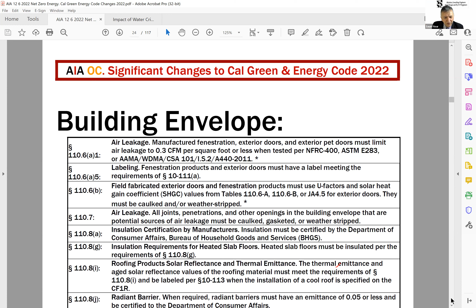There was one item I'm going to beg all of you about: slab edge insulation. It's been there for God knows how long, and I can guarantee most of the contractors have not seen it. Slab edge insulation goes along the slab edge against the earth, whether the slab is 16, 18, or 24 inches, and you put insulation against it. How much insulation? That's all in Title 24. A majority of people have missed it, it's not installed, and nobody puts it in.